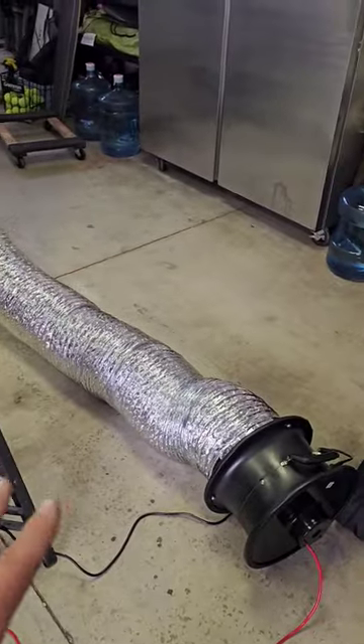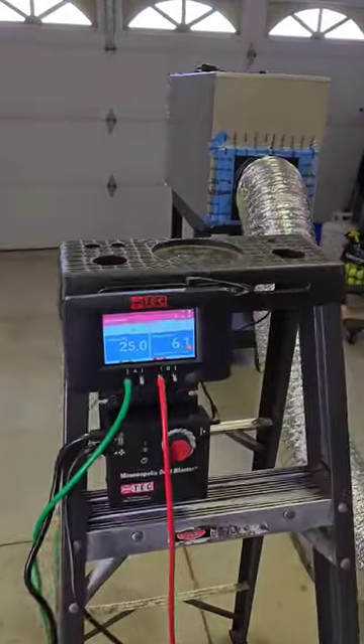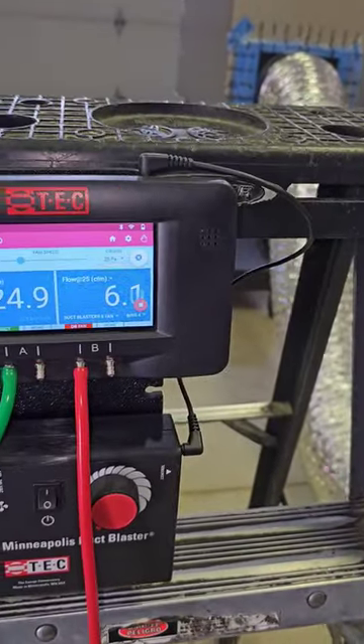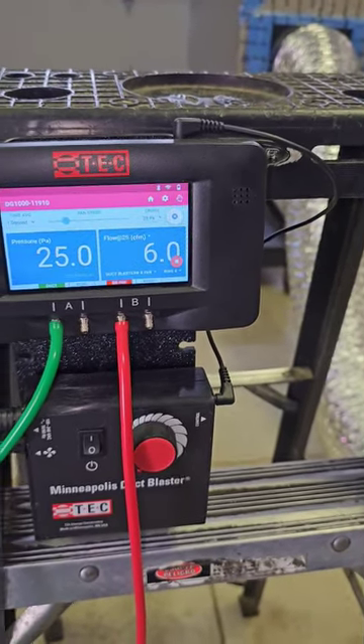Currently doing a duct blaster test, pressurizing my brand new air handler that I'm about to install in my house. It's running right at 5.9 to 6 CFMs of leakage at 25 pascals.